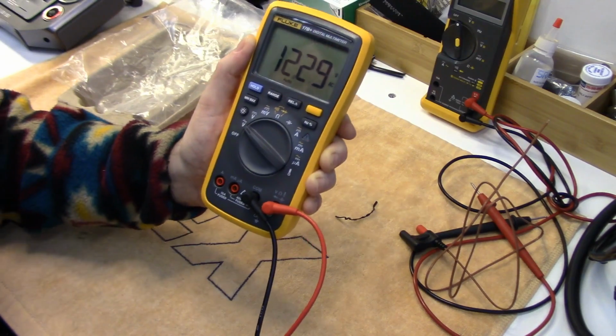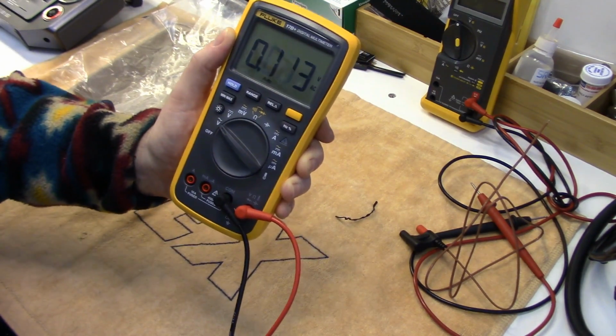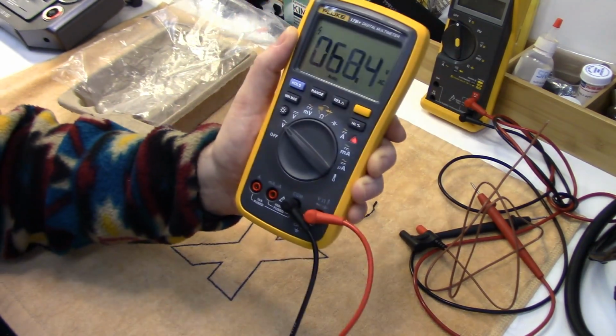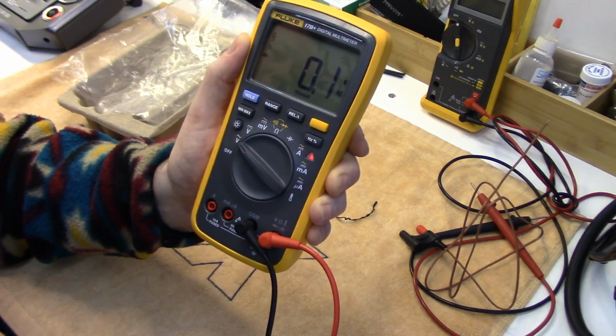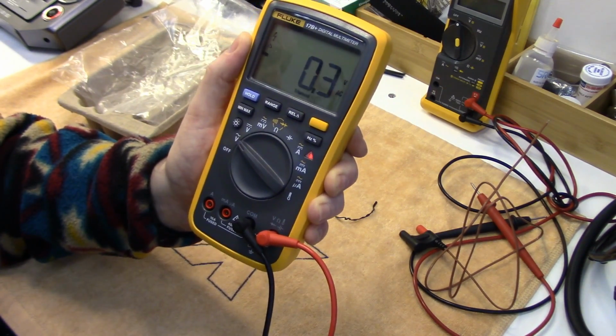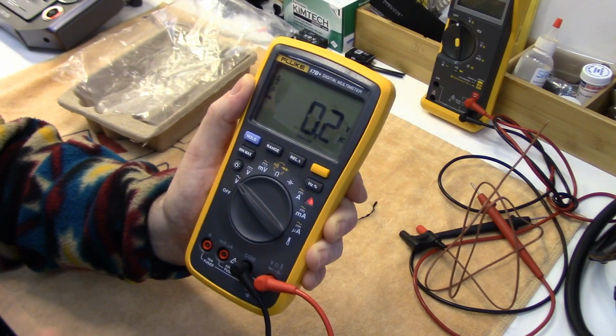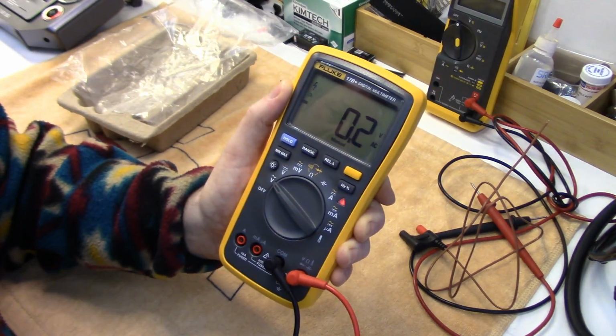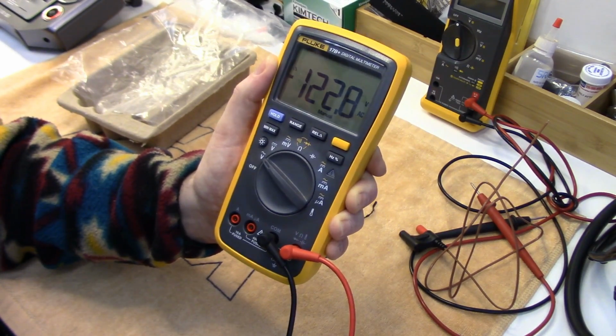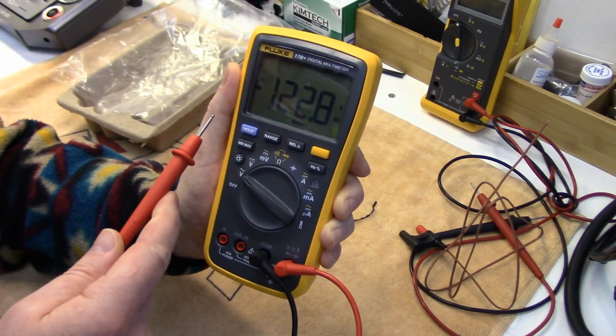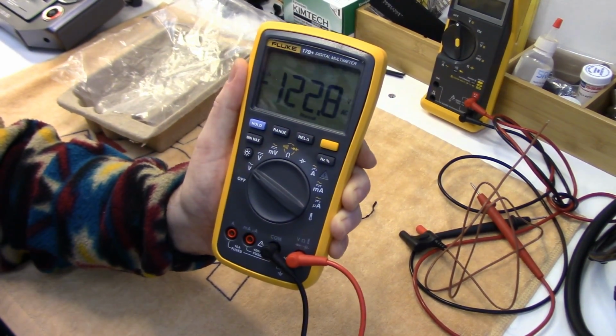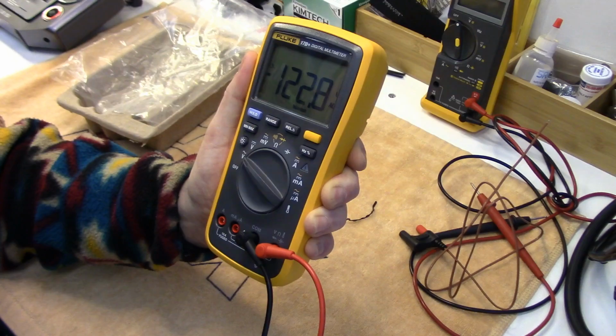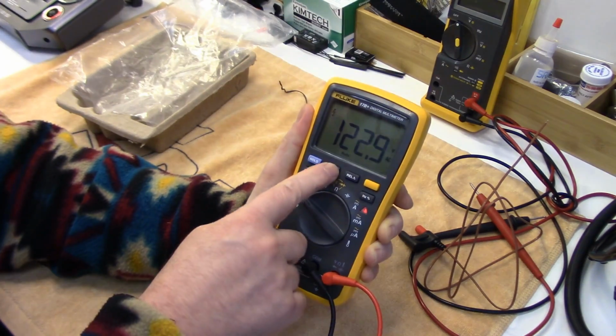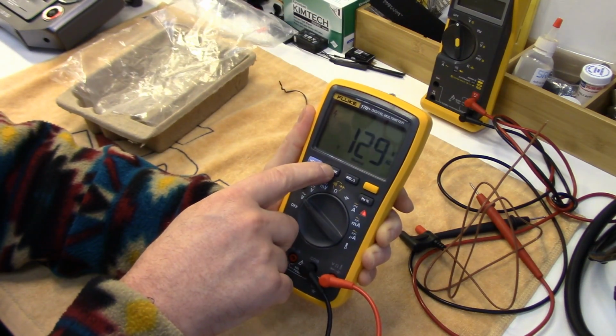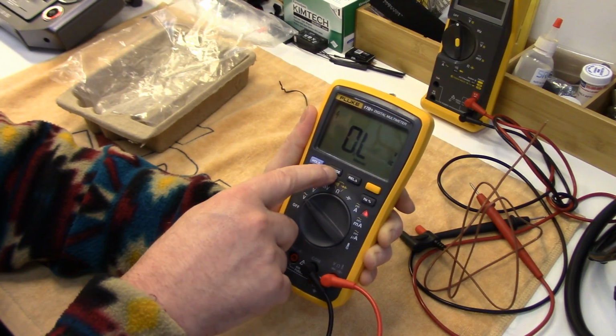The other one is the relative button, which basically zeroes out the value, so any potential voltage or current change will read down from that. So we zeroed it out there, and now, with the probe disconnected, it's reading minus 122.8 AC. Range, you can just change from manual to auto.